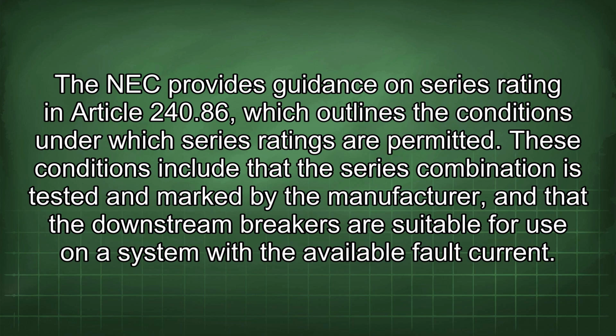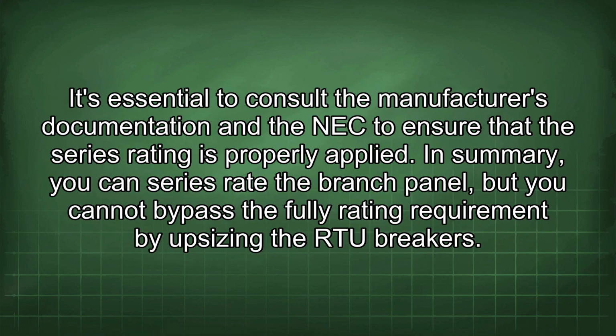The NEC provides guidance on series rating in Article 240.86, which outlines the conditions under which series ratings are permitted. These conditions include that the series combination is tested and marked by the manufacturer, and that the downstream breakers are suitable for use on the system with the available fault current. It's essential to consult the manufacturer's documentation and the NEC to ensure that the series rating is properly applied.